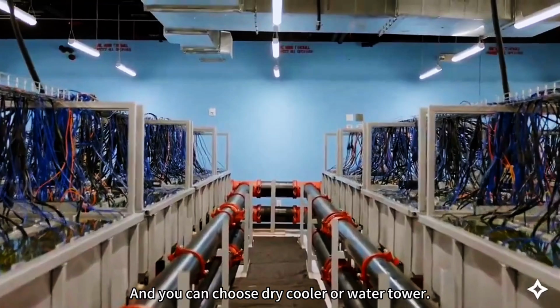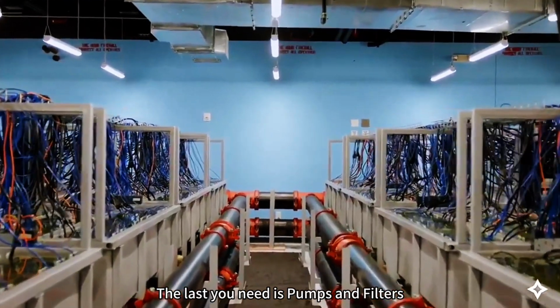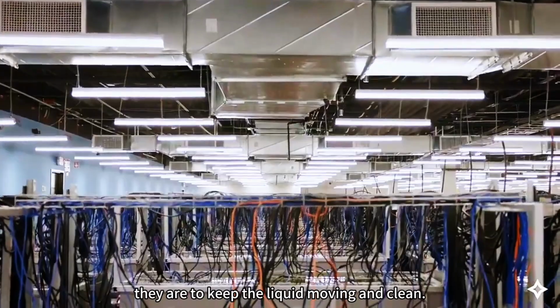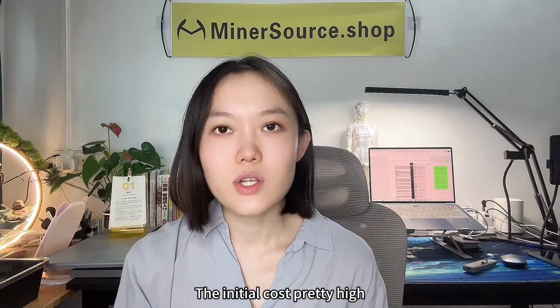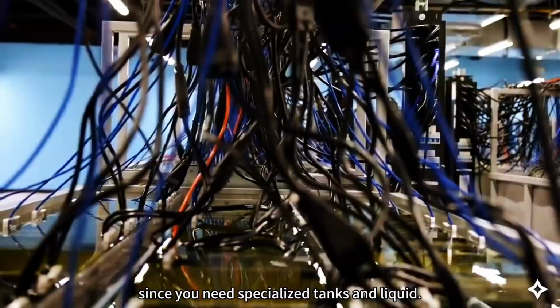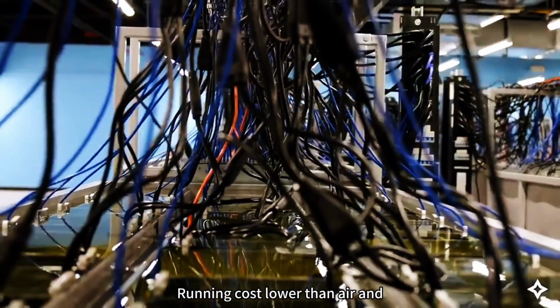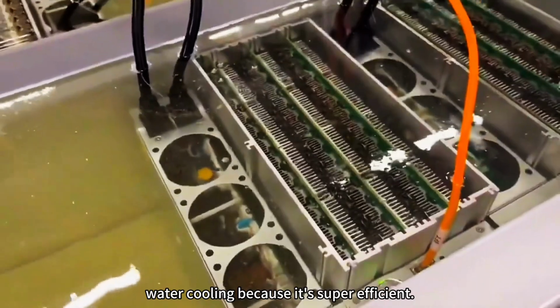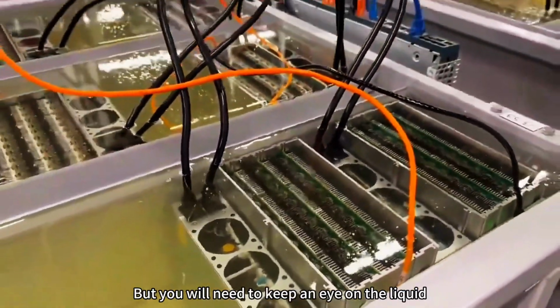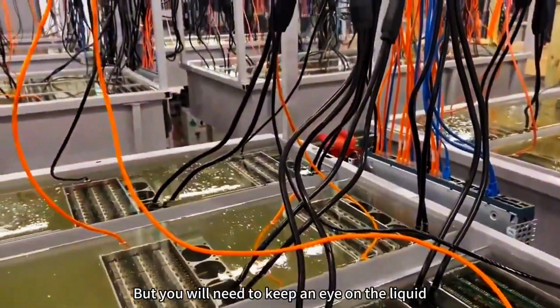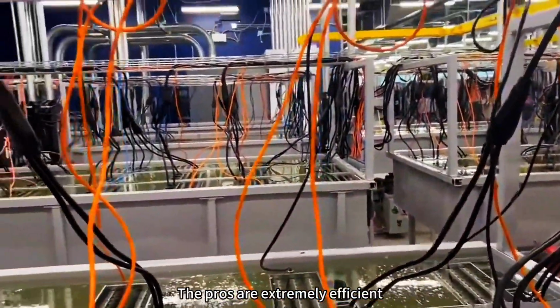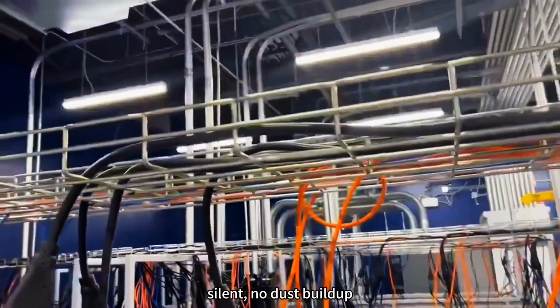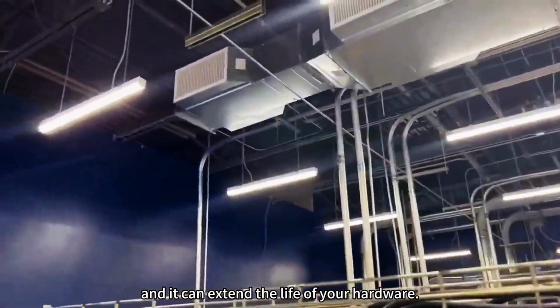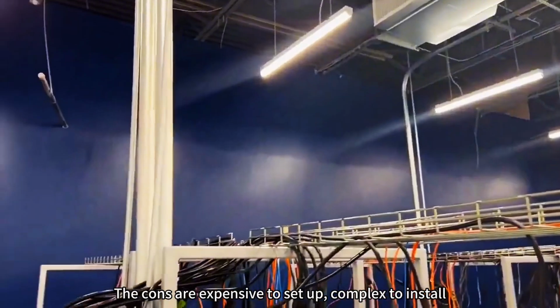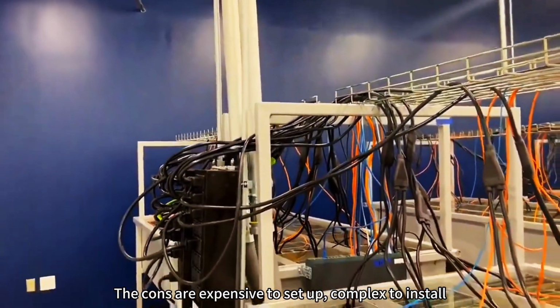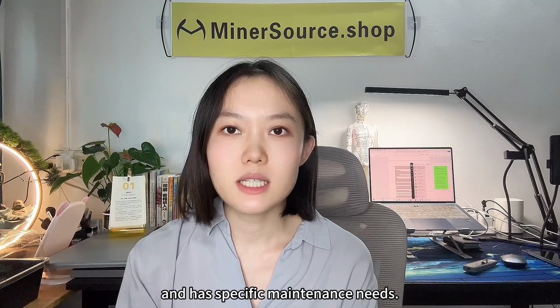You can choose a dry cooler or a water tower. The last thing you need is pumps and filters to keep the liquid moving and clean. The initial cost is pretty high since you need specialized tanks and liquid. Running cost is lower than air and water cooling because it's super efficient, but you'll need to monitor the liquid and change it occasionally. The pros are extreme efficiency, silence, no dust buildup, and extended hardware life. The cons are expensive setup, complex installation, and specific maintenance needs.